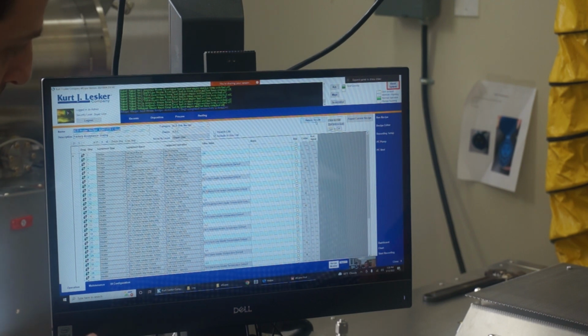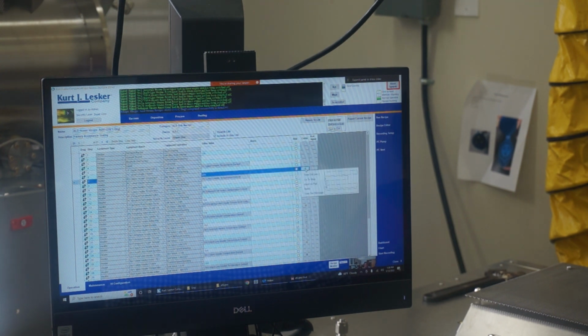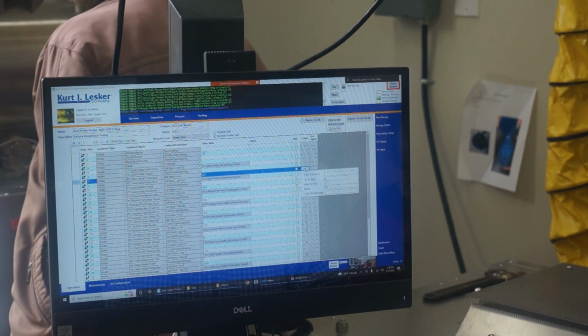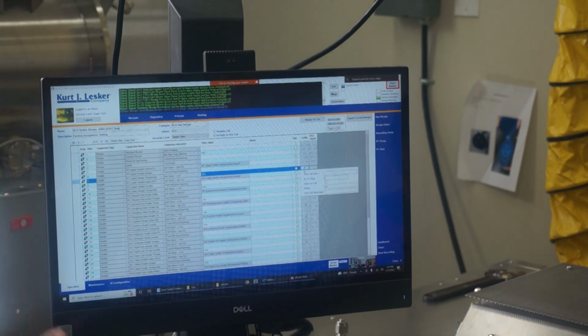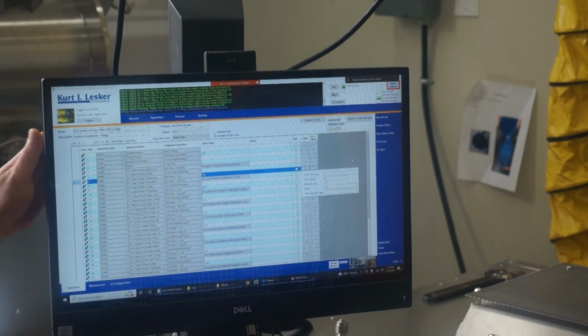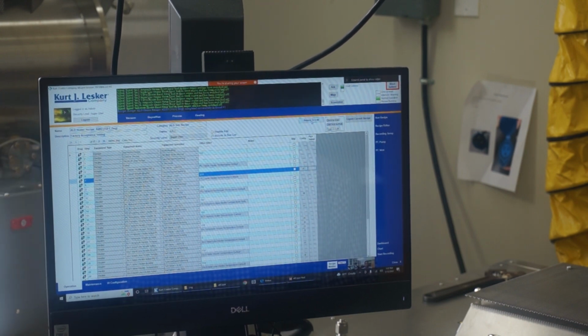Now in the configuration, you see an R on there? RES. Click on that. So in this heating recipe, that's what gives it a ramp rate. Before, on the heater screen, you could put a ramp rate and the set value. This does it in a recipe. That's how it looks whenever you have a ramp in a recipe. That'll be 10 units, or this 10 goes, degrees over a minute. So that R is a ramp.